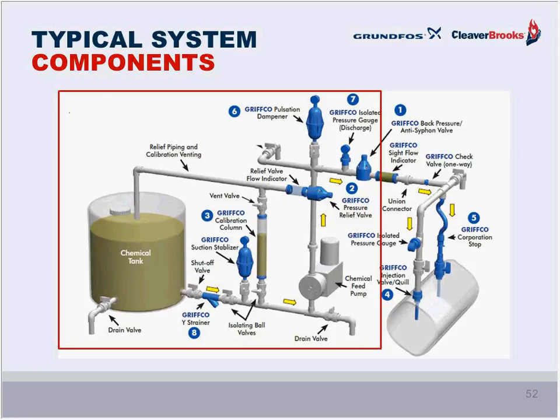And that's the reason. Calibration column. The columns are used to conduct accurate calibration of the metering pumps. Without calibration of the injection, it is first impossible to dose with accuracy. At initial startup and after maintenance, it is good practice to calibrate the metering pumps against actual system pressure. For this reason, most dosing systems come with an integrated calibration cylinder that is appropriately sized for the pumps. It's common calibration or drawdown for 20 to 30 seconds.